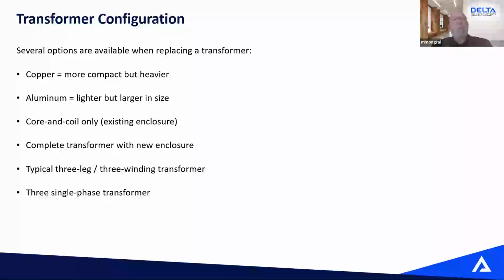Depending on your existing transformer, you might consider different options about winding material. Back in the days, when I started at Delta almost 20 years ago, 75% of the transformers were made with copper, and 25% were made with aluminum. And now in 2026 it's the total opposite. About 75-80% is aluminum, and 20-25% is copper. So just because your existing transformer is made of copper, we don't have to go copper. We can go aluminum, but again, copper will be more compact but heavier. Aluminum will be lighter, but the windings will be a bit larger.